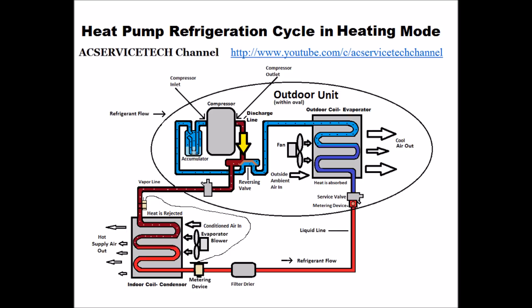It comes through the discharge line to the one side of the reversing valve — the side that has only one pipe attached to it. That is the discharge line. It goes through the reversing valve to the service valve and then out of the outdoor heat pump as a high pressure, high temperature vapor refrigerant. It then comes to the indoor coil, which is now the condenser coil.